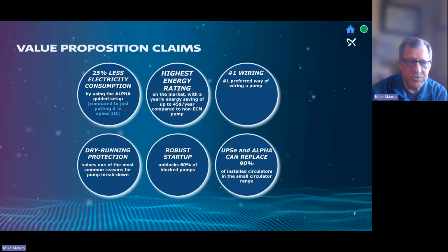So we have quite a few value propositions in these products. The best energy rating of all pumps of their class of this size. If you use the settings within the pump, you can increase the energy efficiency you would save by putting the pump in the mode that would run the most efficient and the best for that application. We'll go through how that works in a little bit. Wiring is an improved wiring system, and it's an awesome wiring system for ease of installation. The pump does have dry run protection. All of these pumps that we're going to go over have dry run protection. First, for a pump of this size, robust startup, and the UPSe and the Alpha together can replace 90% of the pumps on the market that are in this size. So back to the old 1 pump on the truck.